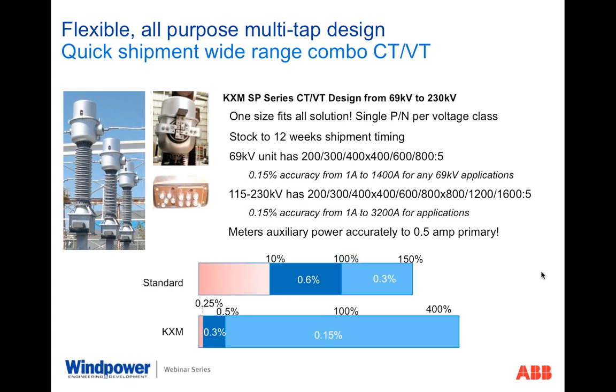So out of one unit at 115 kV, one part number for every 115 kV system out there, we have one part number that will be supplied that meters accurately any current from 1 amp to 3,200 amps. Depending on your site system condition, you just take it to the site and reconfigure the ratio requirements specifically for that site. And so this has been very popular because short lead times, anywhere from stock to 12 weeks, has been able to help support the development of the wind farms in a much faster mode. And believe me, when you're facing the incentive credit deadline, that lead time is important.